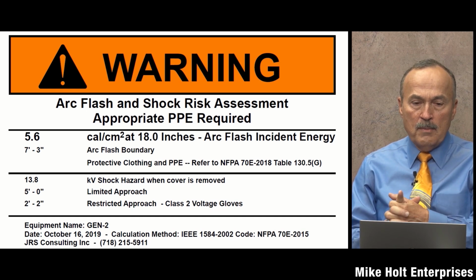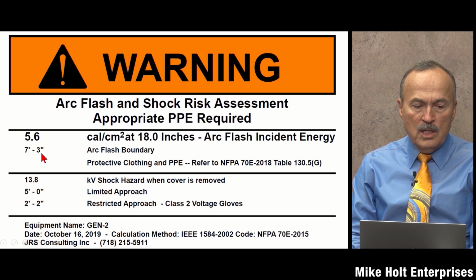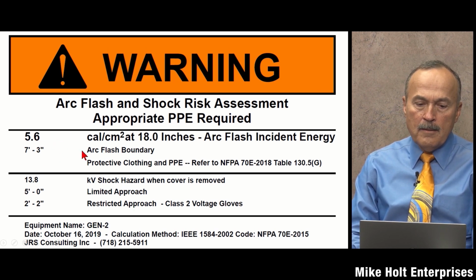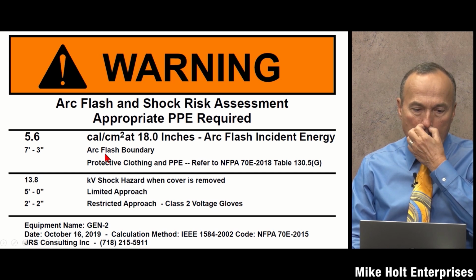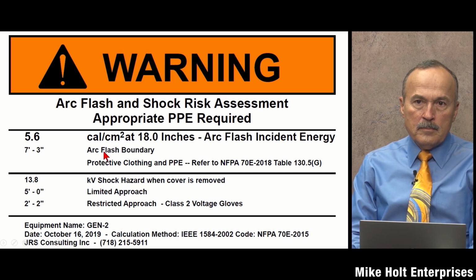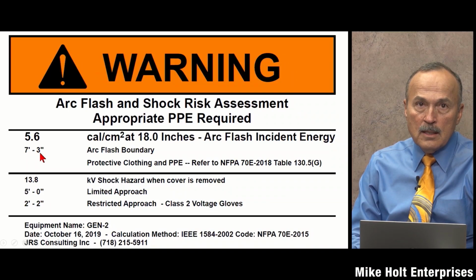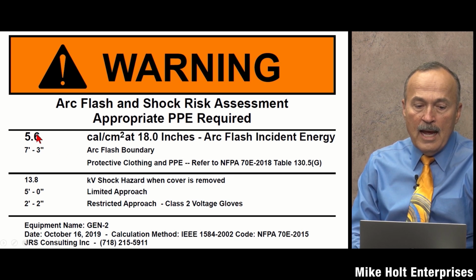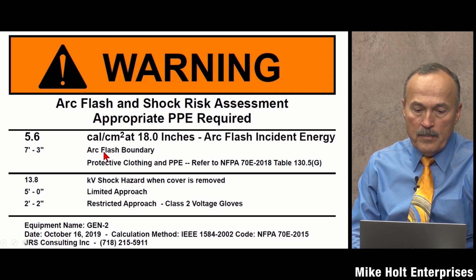And we're going to show some pictures. We'll talk about the arc flash boundary. So Jennifer, help me out here. The 7 feet 3 inches arc flash boundary, is that the distance I have to use the 5.6? No. That is the onset of second degree burns. Anytime you're walking inside that area, you have to be dressed at a level of incident energy, which is calculated at the 18 inches. So if I'm within 7.3 feet, then I have to use the 5.6 minimum rated calorie in that area.